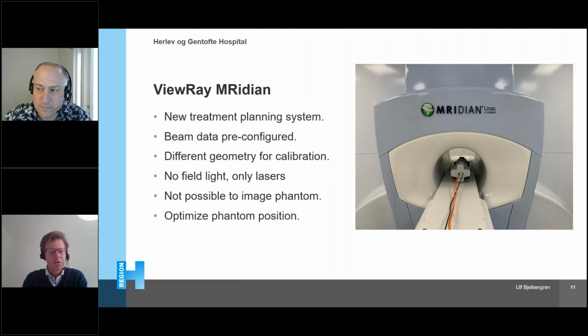Do you perform optimized phantom position based on the plan or beforehand based on a 4 field box plan? No, we use that on the plan. Yeah. Okay. And of course, for example, machine QA and so on, we have other methods of securing that. We have imaging detectors in the right place. The MLCs are performing as planned, and so on. So the machine QA is differentiated from the patient-specific QA. Me personally, I'm not worried about the phantom being misaligned by 1 to 2 millimeters, because we have track of that on the machine.